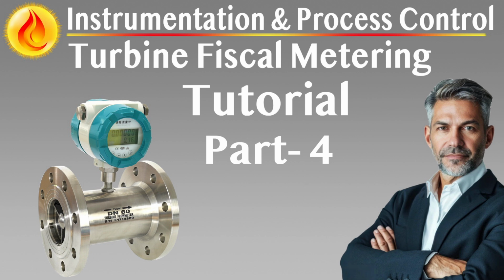Following a successful proving sequence, the newly calculated meter factor must be displayed for operator review. Upon approval, the factor must be automatically or manually downloaded to the corresponding stream microcomputer. The previous factor must remain stored for historical comparison, and any changes must be timestamped and recorded with operator identification.